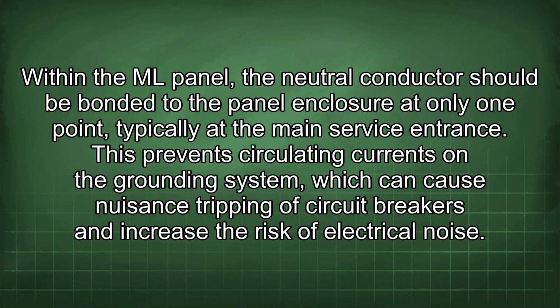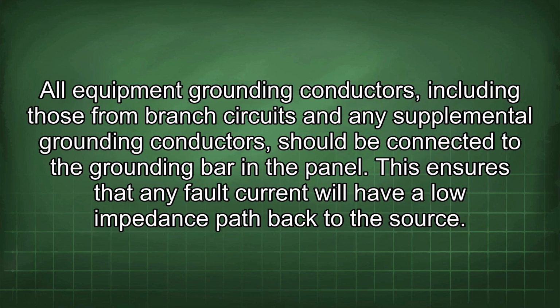This prevents circulating currents in the grounding system, which can cause nuisance tripping of circuit breakers and increase the risk of electrical noise. All equipment grounding conductors, including those from branch circuits and any supplemental grounding conductors, should be connected to the grounding bar in the panel. This ensures that any fault current will have a low impedance path back to the source.